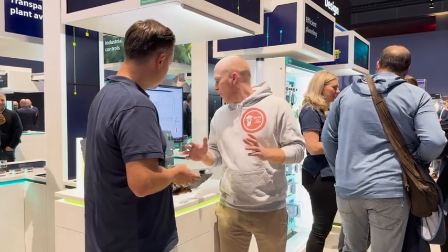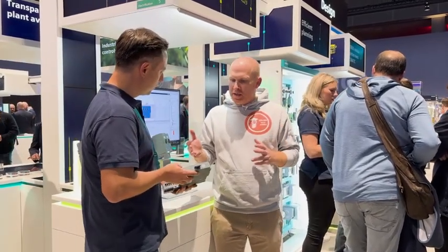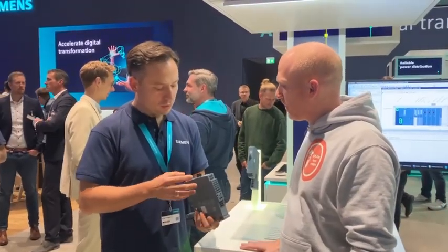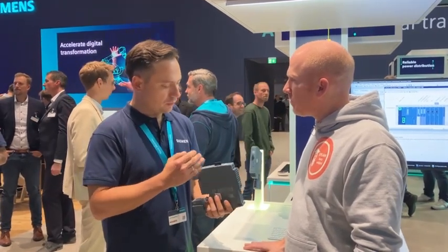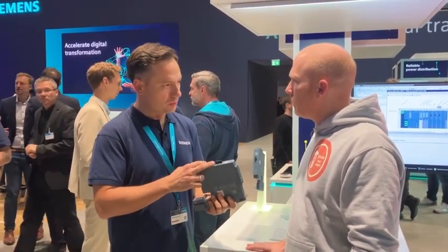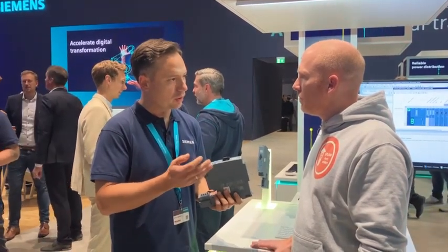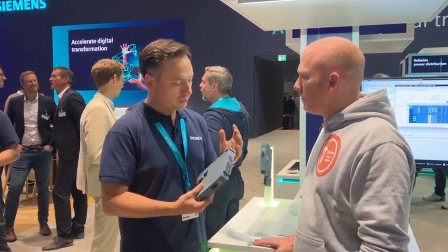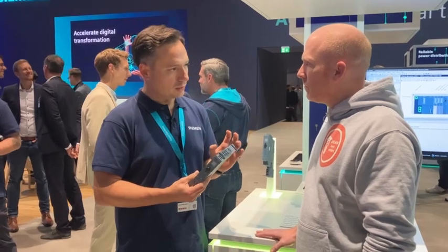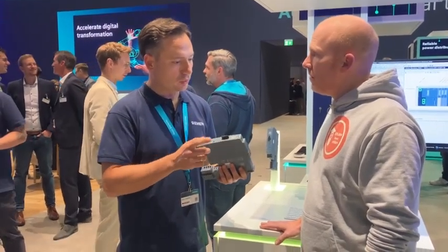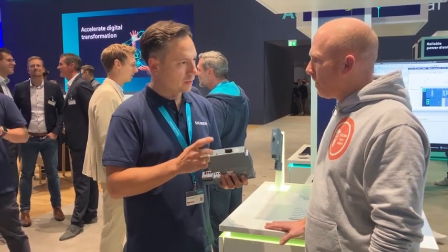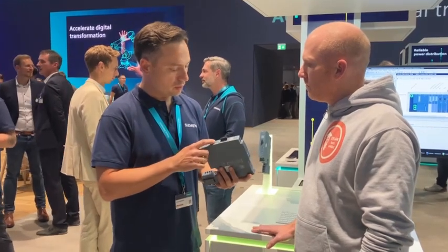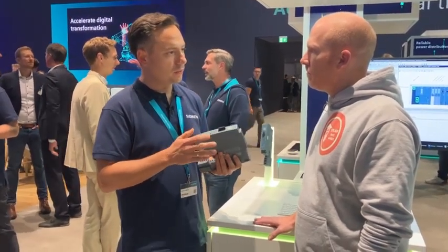That's correct. Maybe we can have a look at the function, because as far as I know, it's based on semiconductor technology. Is there something special about this technology? As we said at the beginning, it's fully electronic. This means the electromechanical component is no longer here for switching off the load in case of a short circuit, and that's exactly the biggest advantage of this technology. In case of a short circuit, we can shut it down about 1,000 times faster compared to a normal fuse or circuit breaker that we have today. So we're working in the microsecond range. The short circuit disconnection occurs in about 4 microseconds.